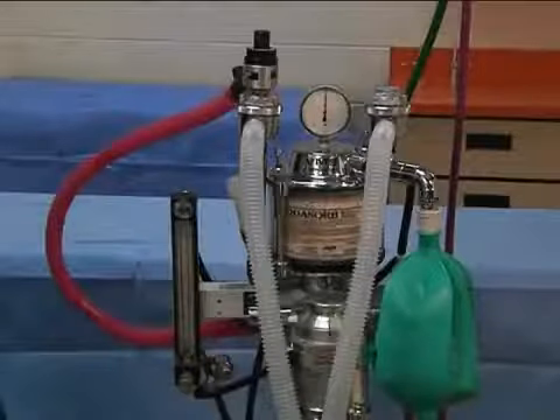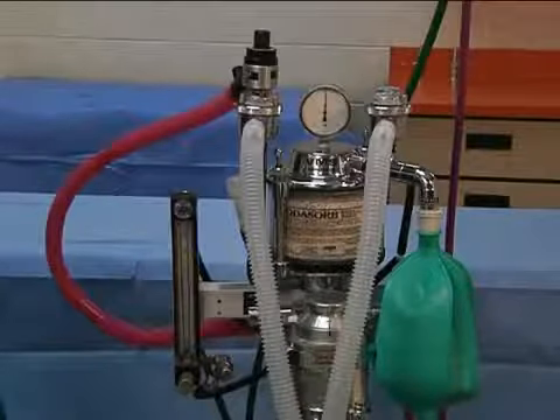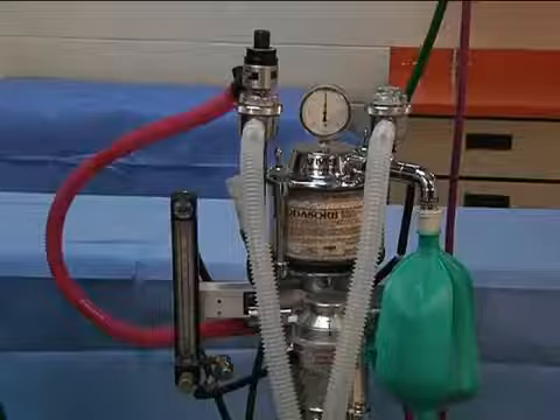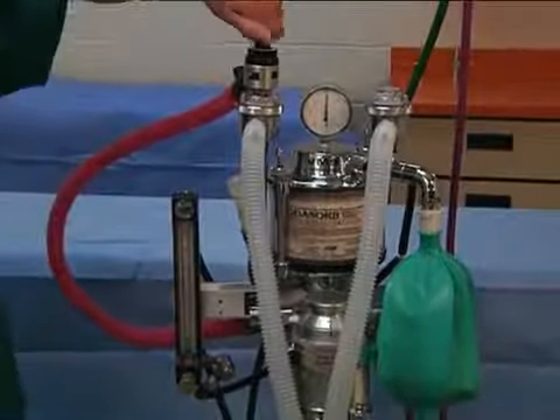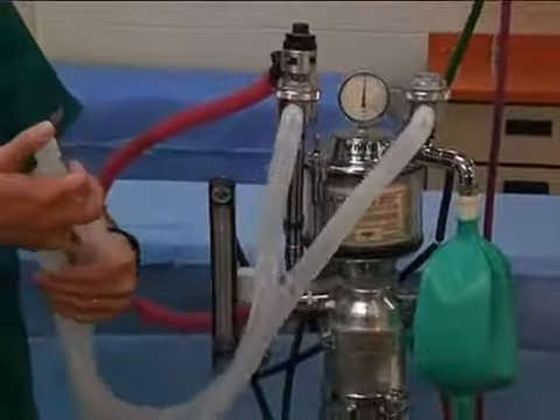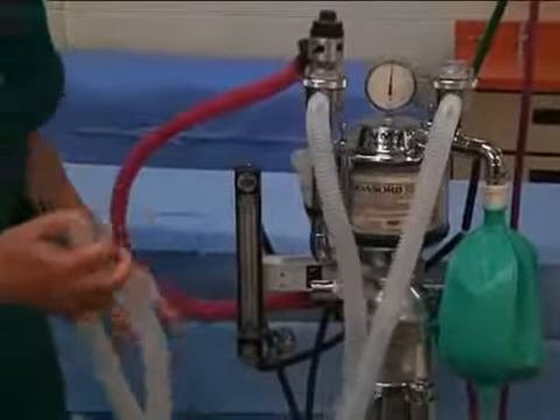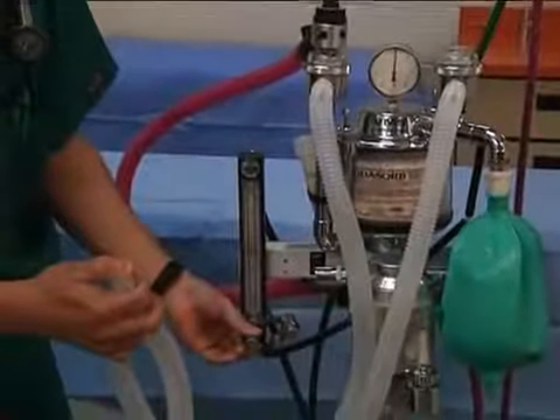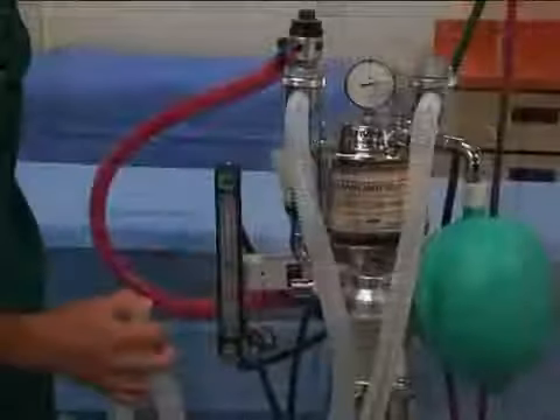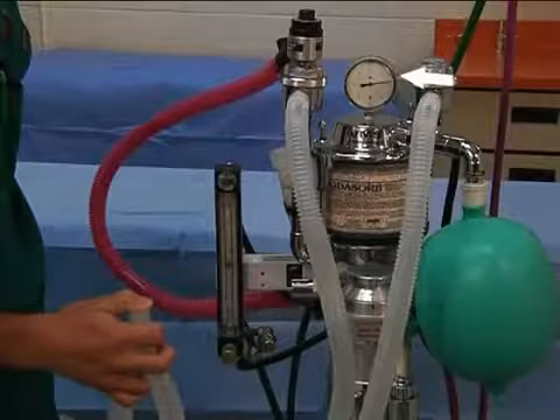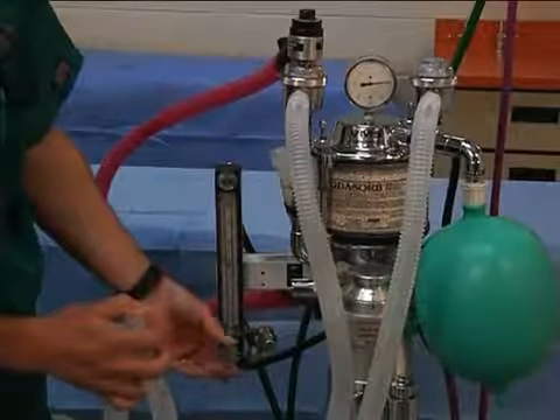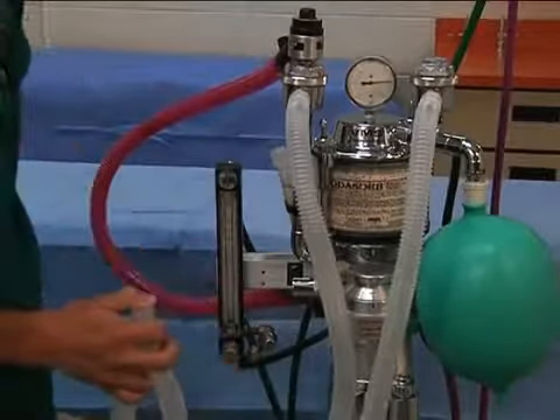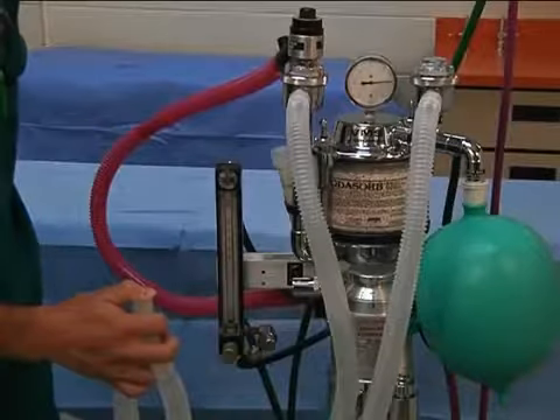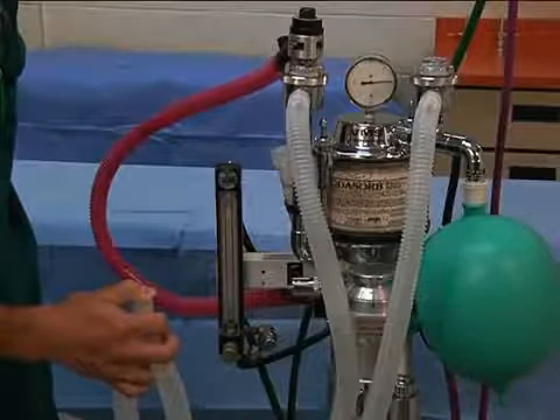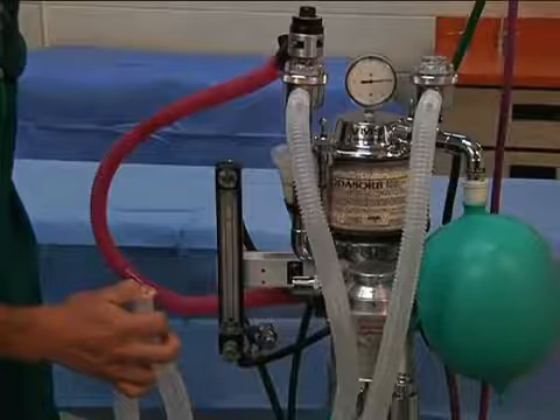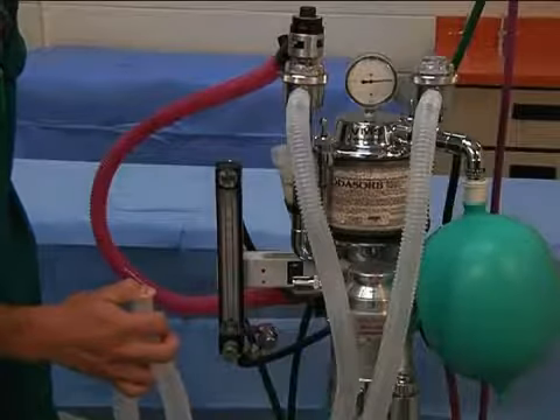The anesthesia machine and breathing circuit must be checked for leaks before connecting to a patient. Close the pop-off valve and occlude the Y-piece using your thumb. Turn on the oxygen flow and wait until the circuit pressure reaches 40 centimeters of water. Next, turn off the oxygen flow and observe the pressure gauge on the circuit. If the pressure in the circuit cannot be maintained over 10 seconds, check for leaks in the circuit.